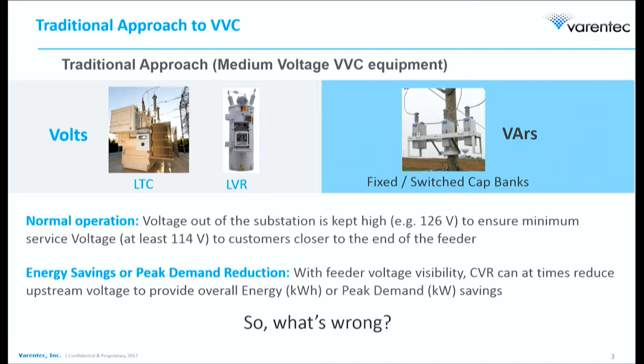So just to walk through how this starts and where we are today: typically, power distribution has been to supply as high a voltage out of the substation as possible, so your lowest voltage customer still has voltage within the ANSI limit, which is 114 volts. So you end up with, for example, 125 or 124 volts out of the substation, so your lowest end customer has 115 or 114 volts.